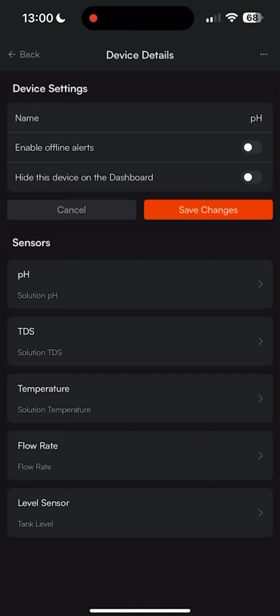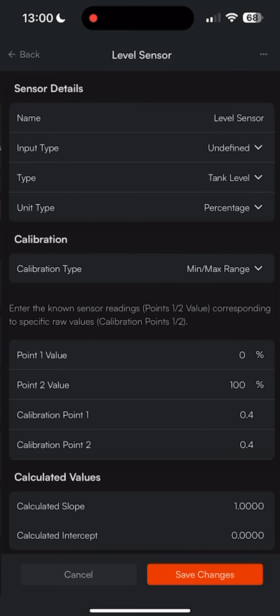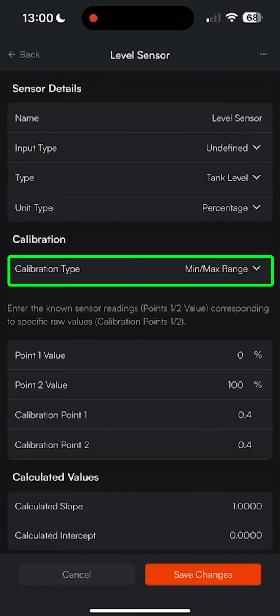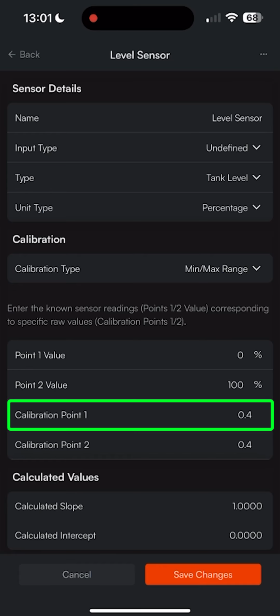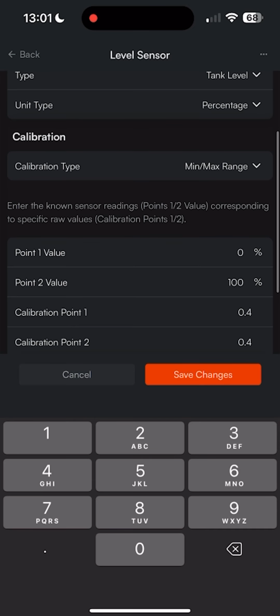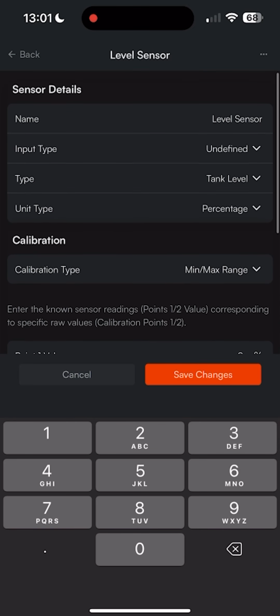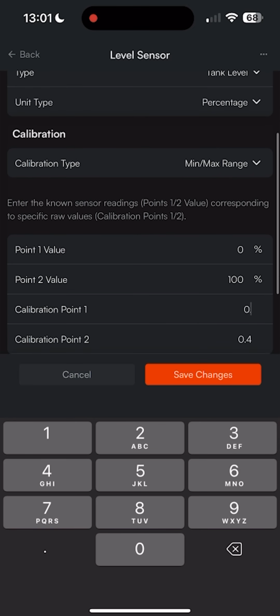Lastly, for sensors like tank level sensors or par level sensors that have a defined min and max range, we can use the min-max range calibration type to calibrate those. We can start by tapping the sensor itself, using the min-max range calibration type, and then inputting the range of values that sensor is spec'd to have from its datasheet between two different endpoints.